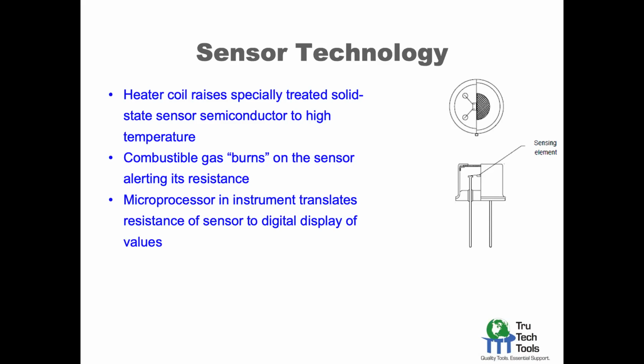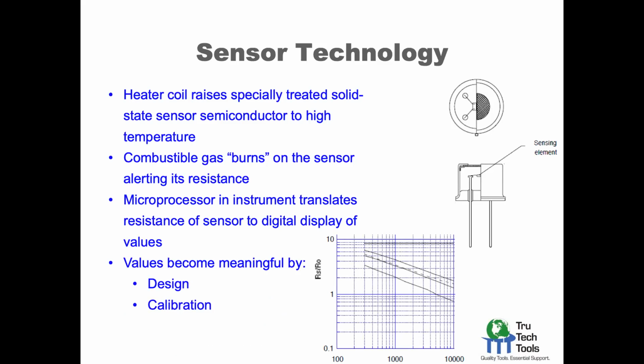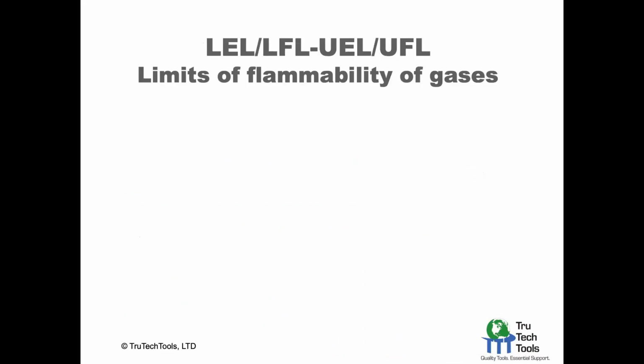So that's what's actually being calibrated here, is how much does the resistance in the sensor change compared to the gas concentration. And these values become meaningful. It's not just a shot in the dark here, but there's very scrupulous design. There's calibration that's required to get the digital number out. What you're looking at here is the sensor. This is actually a screenshot from a sensor specification. It's actually a logarithmic response. So it has to interpret that logarithmic response in order to give you the concentration.